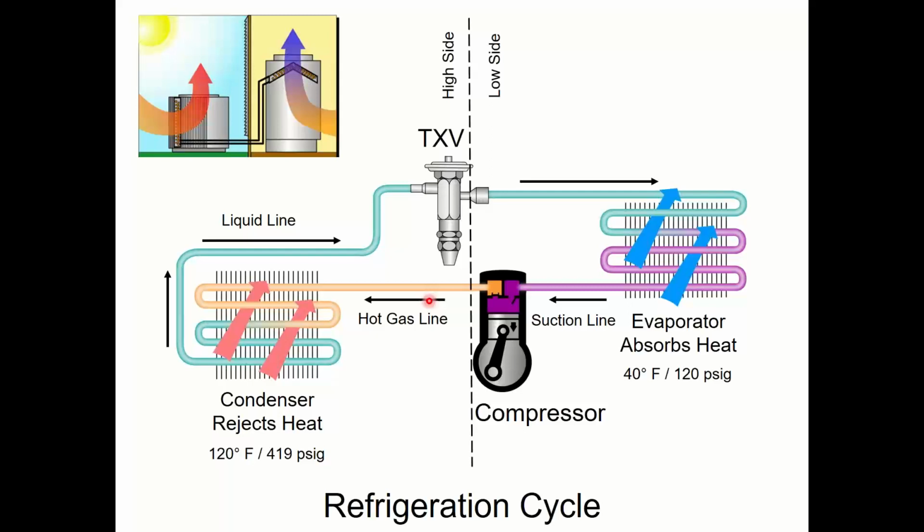And if you remember, when I go from low pressure on a fixed volume thing to high pressure, the pressure goes up, the temperature has to go up. That's also counterintuitive. When you're cooling my building, why are you trying to make hotter refrigerant, Ryan? What are you doing? Well, the reason I'm doing that is because I have to respect the heat always goes from hot to cold rule. It was easy over here because I have 75-degree air and a 40-degree coil, so heat goes from hot to cold, no problem, makes sense.